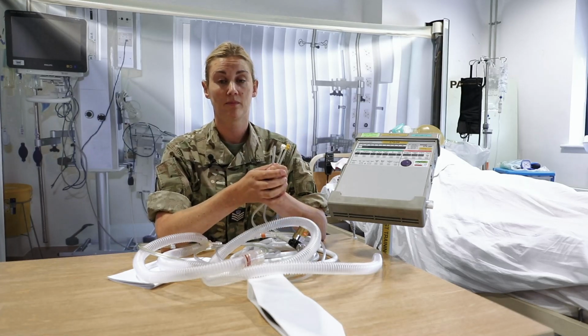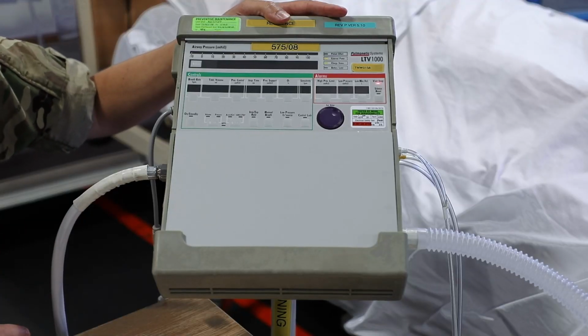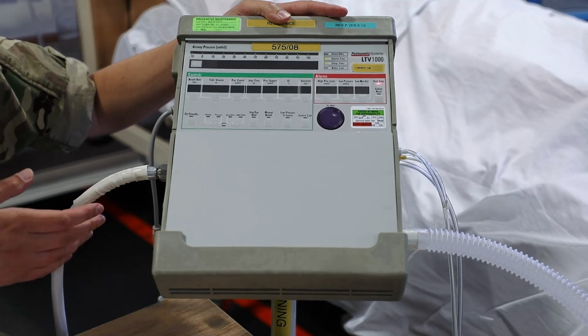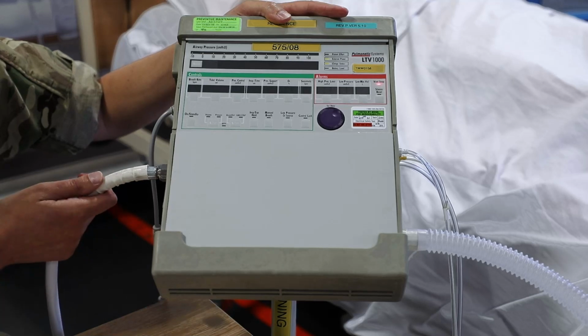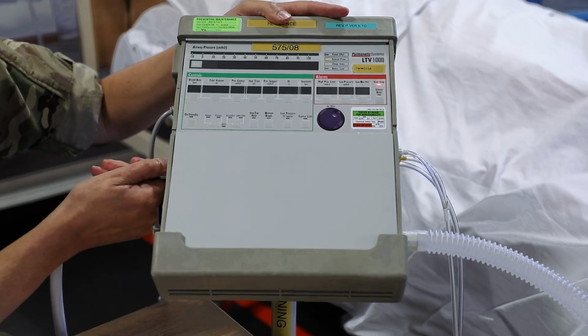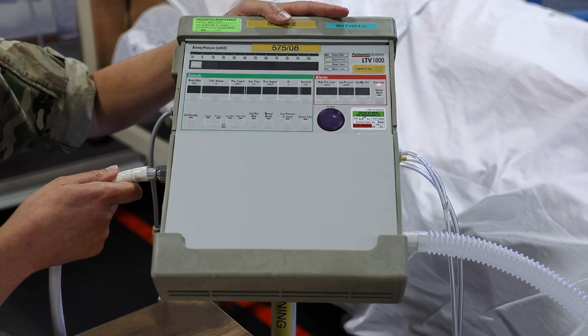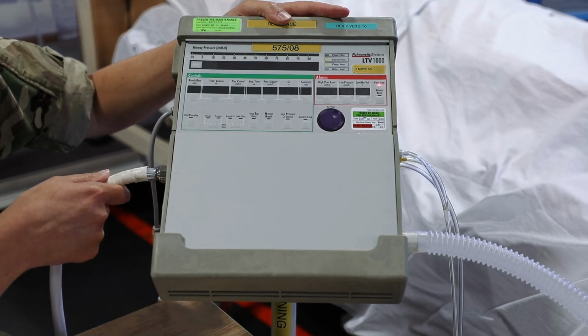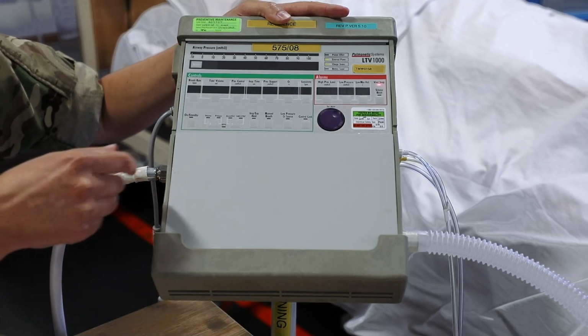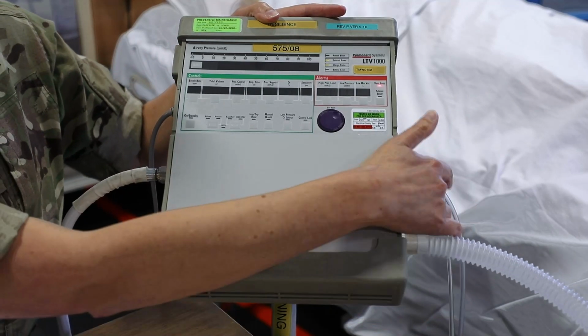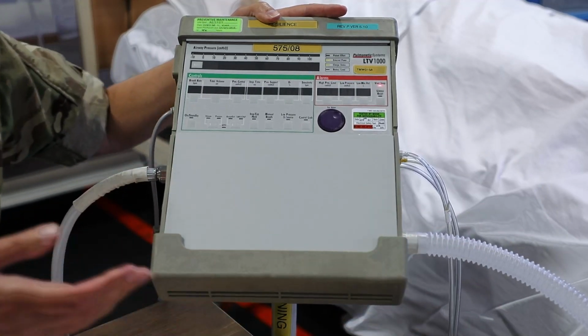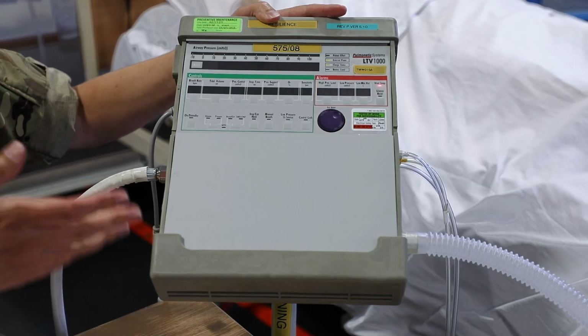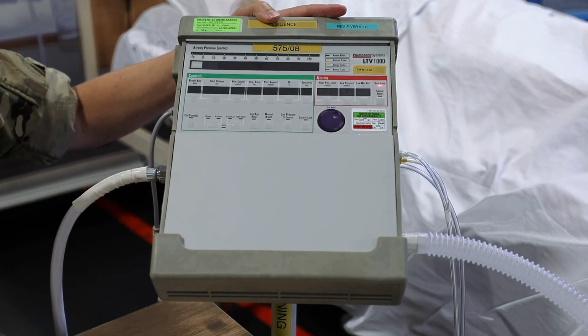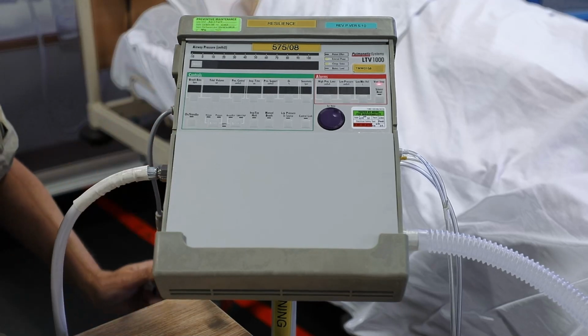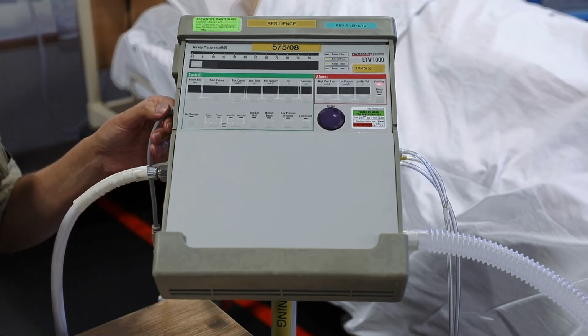Having completed the physical checks of the ventilator, we can move into the functional checks. To perform these functional checks, you should make sure that the oxygen hosing is connected and tightened, and that this hosing is connected to an oxygen cylinder which has some oxygen in it, because we're going to need to check that in a minute. You need to make sure that the patient hosing is all connected and the transducers are correctly connected. You'll have an opportunity to practice making these connections whilst on the course.